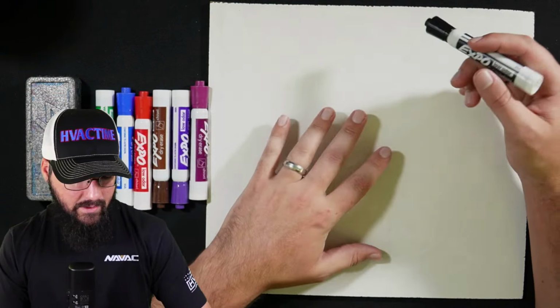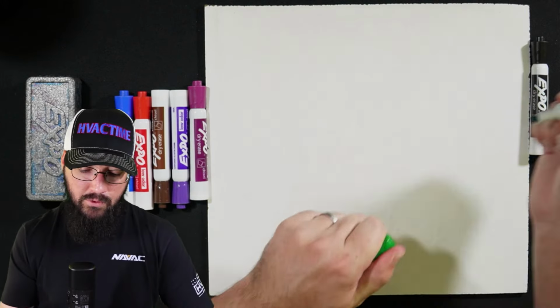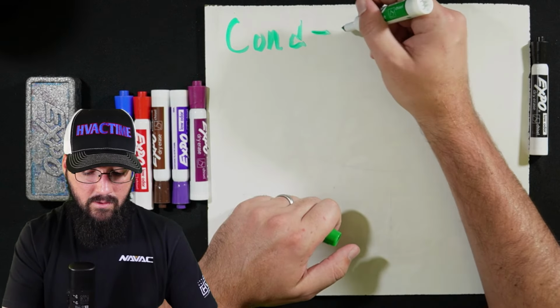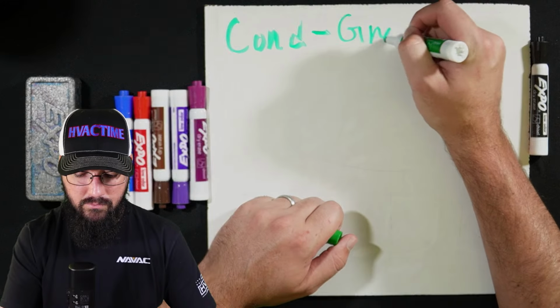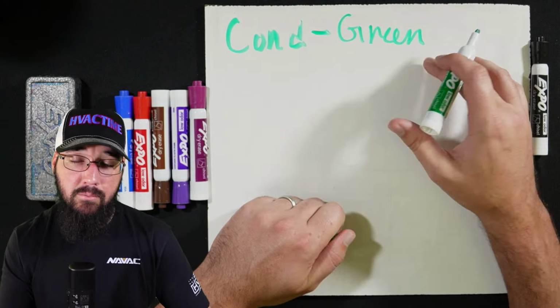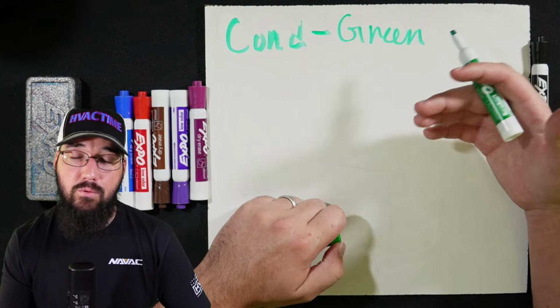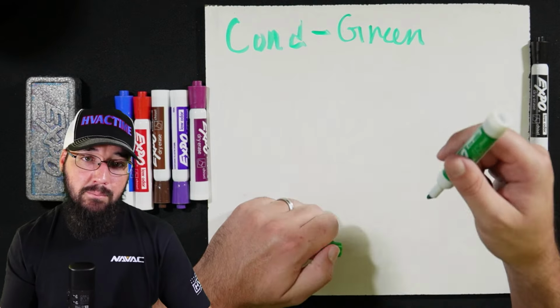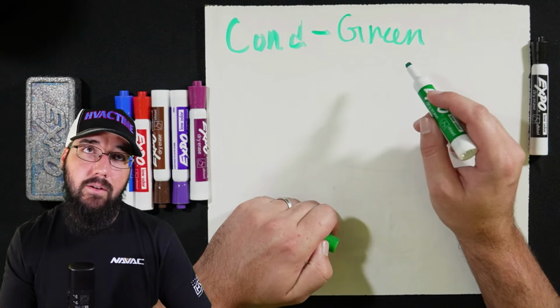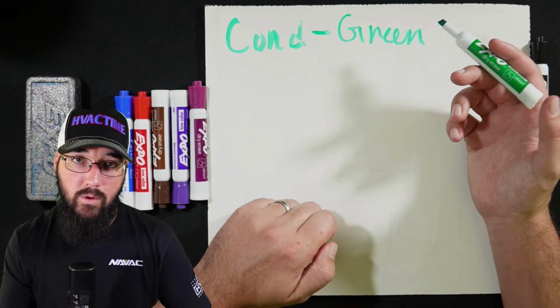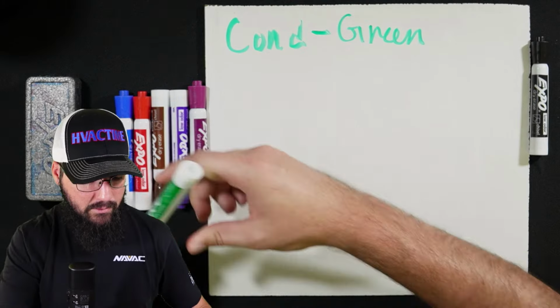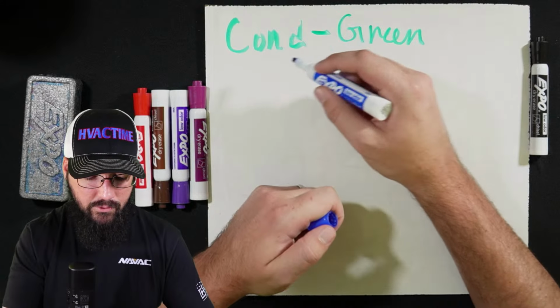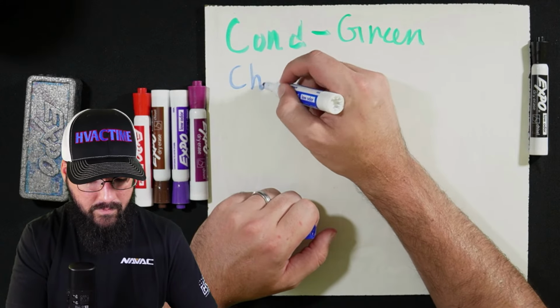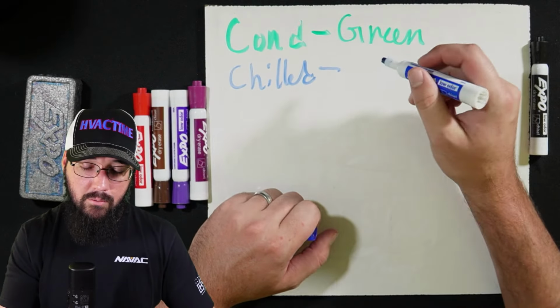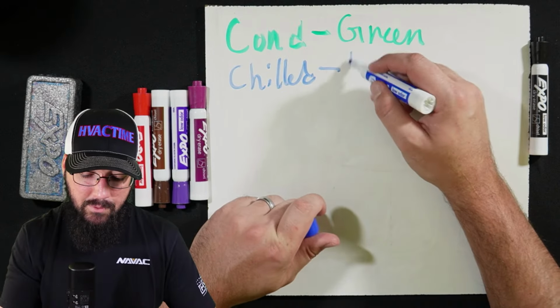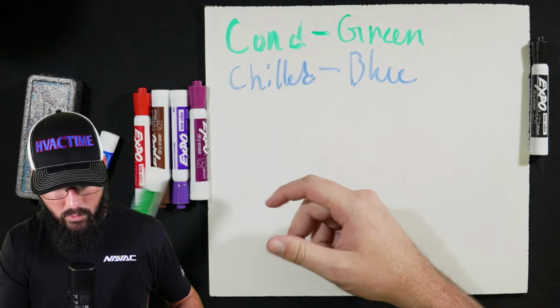So usually condenser water at minimum will almost always be green. This is usually not insulated. Many times the chill water loop will be insulated, and it will depend on the plant. In some plants, they may paint the chill water green as well. In other plants, they might paint it blue. So you'll have either a single color or two shades of blue. Chilled water, and this is non-potable, so both of these are non-potable, by the way, will sometimes be blue and or green.